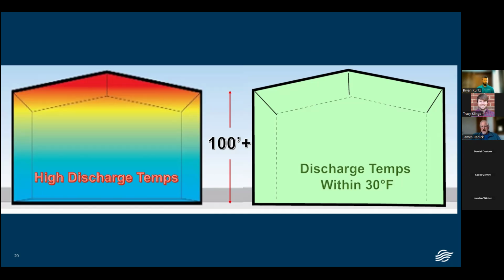But on a minus 14-degree day, they were measuring about 1 degree between the floor and the ceiling. And what we find is that if you turn off the lights and measure that temperature, that stratification level goes away completely. Many years ago, when light systems were less efficient, we would then measure 2.5, 3 degrees, and we thought our system was doing that. But then we did more study, learned as we went, and with our system, you don't create stratification. So any stratification there would be basically the byproduct of some wasted heat energy from inefficient lighting. But how incredible is that?